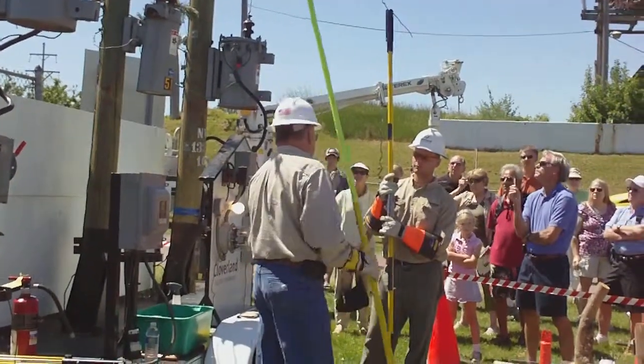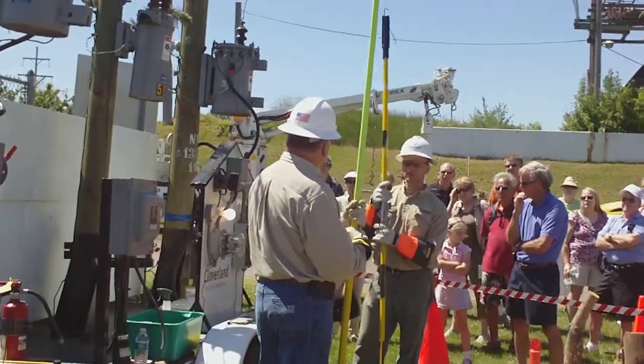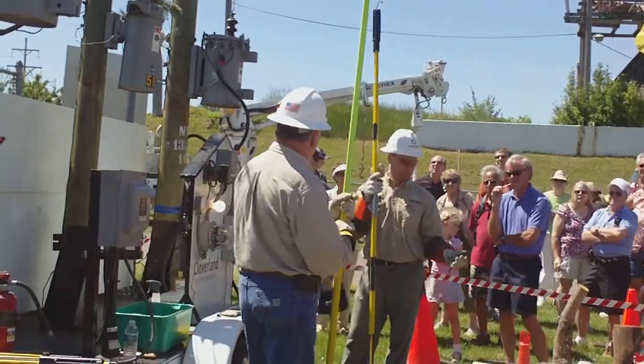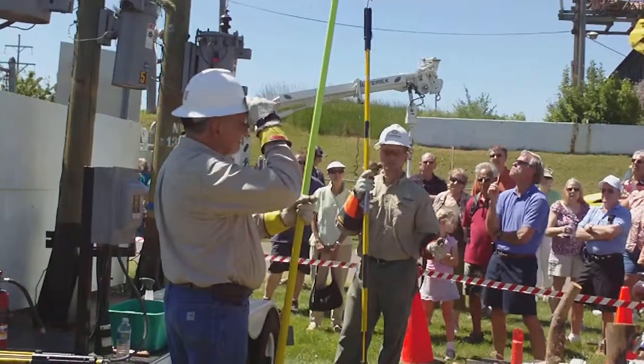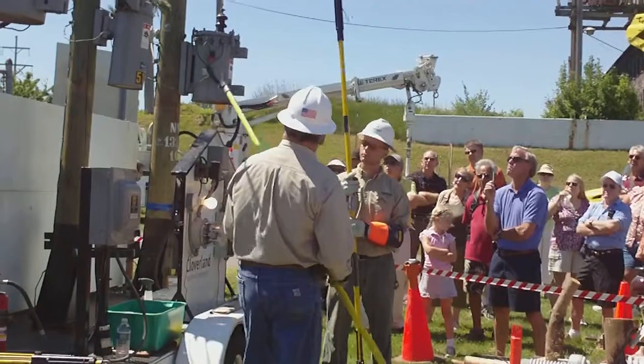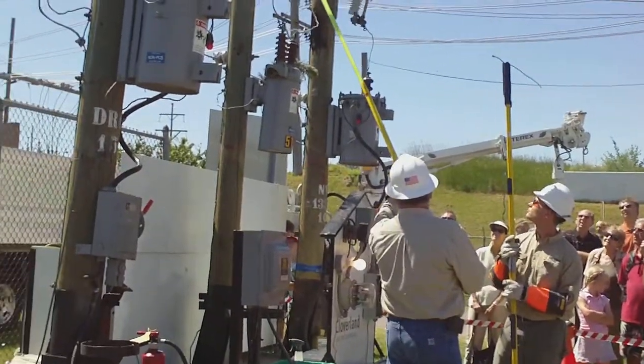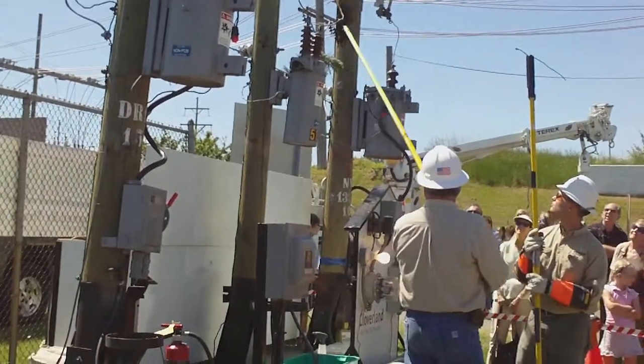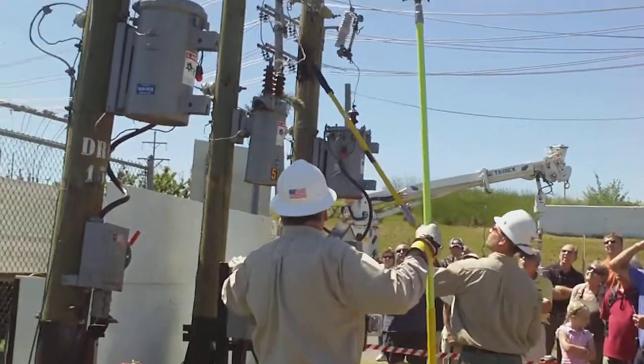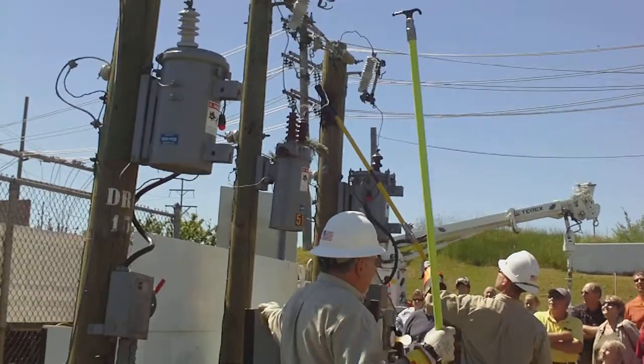These epoxy insulators, do you have much trouble with them? I have. Some trouble with them. They get sun damage just like anything else and break down over time. Okay, with that being said, sometimes if the wires break down in their insulation value, we will get the same as that primary voltage going down and touching that pole. What do you think, Dan? That's basically what we get.